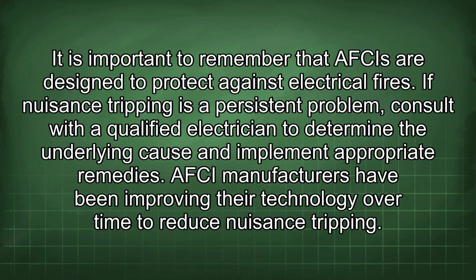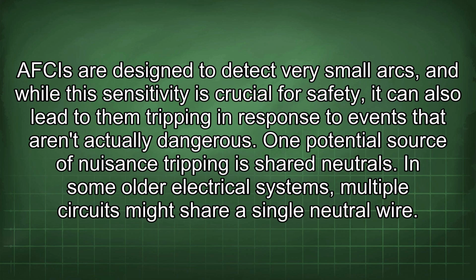It is important to remember that AFCIs are designed to protect against electrical fires. If nuisance tripping is a persistent problem, consult with a qualified electrician to determine the underlying cause and implement appropriate remedies. AFCI manufacturers have been improving their technology over time to reduce nuisance tripping. AFCIs are designed to detect very small arcs, and while this sensitivity is crucial for safety, it can also lead to them tripping in response to events that aren't actually dangerous.